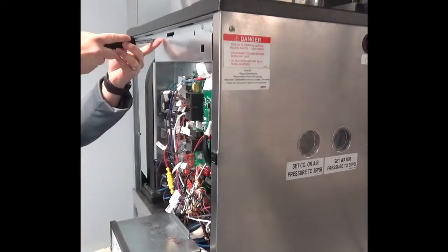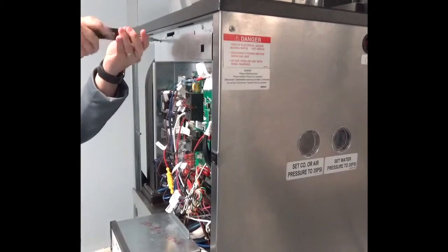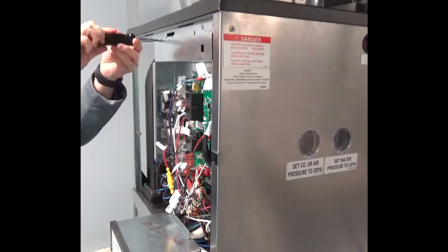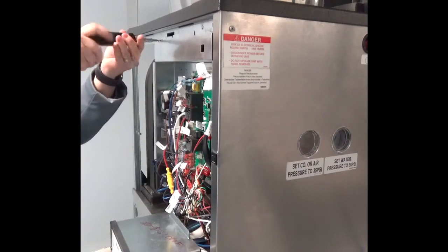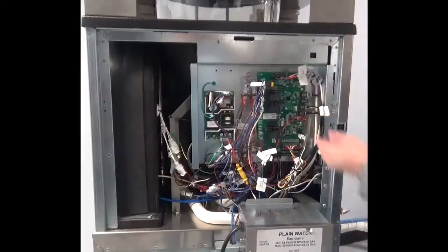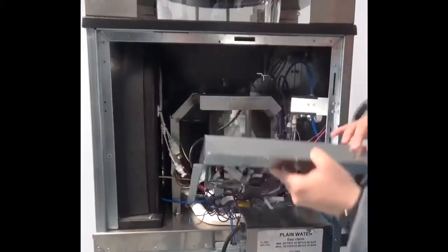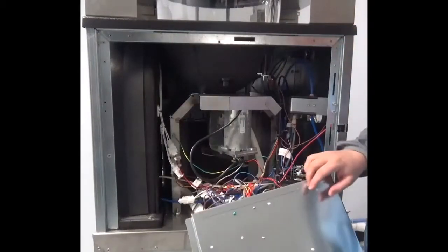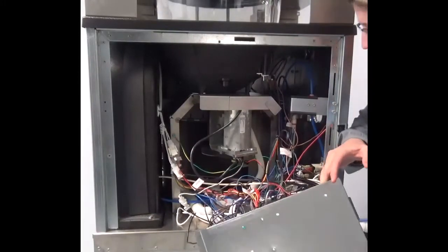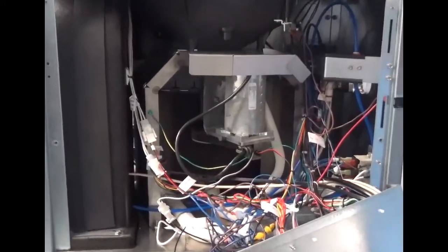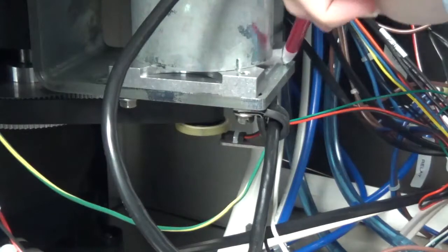To remove the mounting bracket that contains the power supply, relays, and SRB, remove the screw that secures the mounting bracket to the unit. Slightly lift the bracket, releasing the right side hinge, then carefully lower the bracket down towards the lower refrigerated cabinet. Mark the position of the motor on the mounting bracket by marking a line along the edge of the motor onto the mounting bracket.